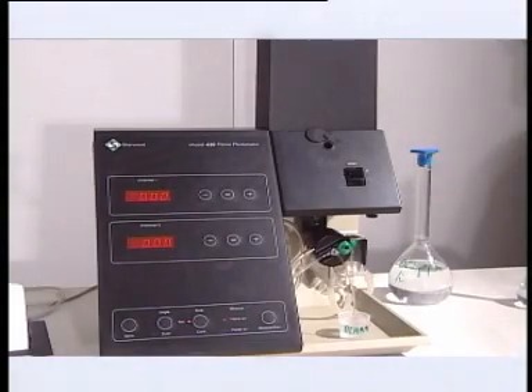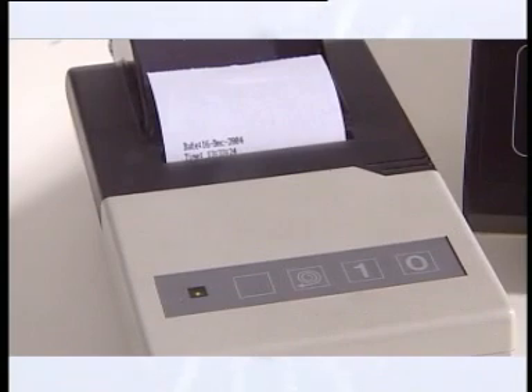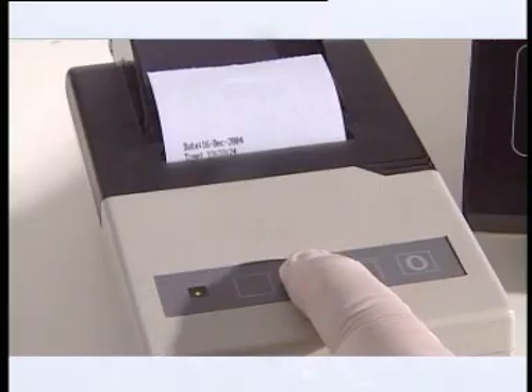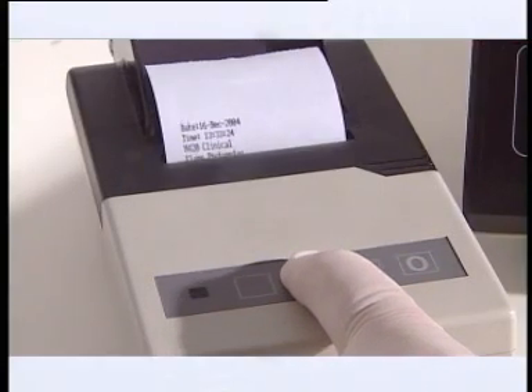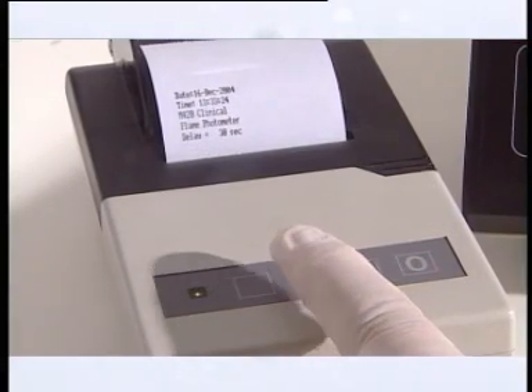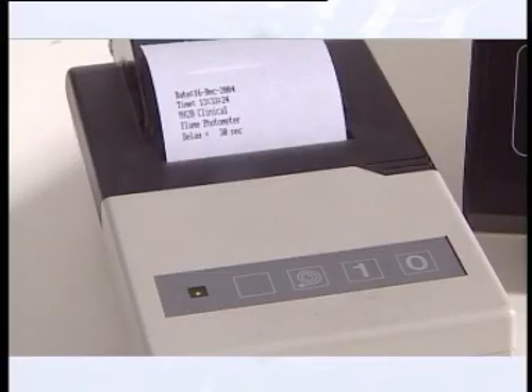The Model 420 features fully automatic ignition and optimization of the flame and intuitive guidance of the user through blanking and calibration. The powerful microprocessor and memory retains calibration data and prints out date and time of each analysis through the RS-232 serial port. The printout also includes drift information, which is compensated by the internal standard.